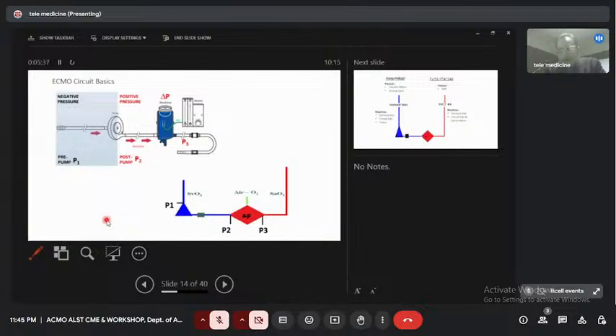So there are a few parts in the circuit that are important to understand. On the extreme right side, okay, you harvest the blood from here with the pump. So this part will be negative, okay. This is known as pre-pump or P1 pressure. And after you harvest, you mobilize with your centrifugal pump and push it. Then this is the oxygenator. This is your pre and post, okay. P2 and P3. P2 is your post-pump but pre-oxygenator, and this is your post-oxygenator, okay.